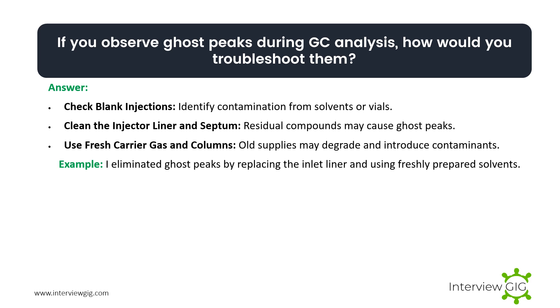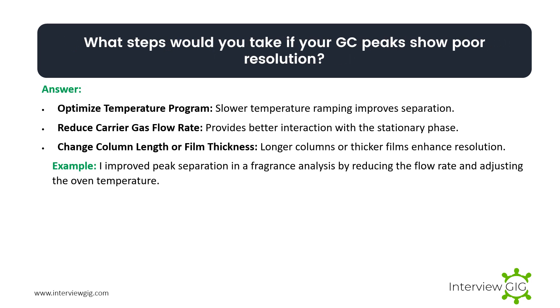If you observe ghost peaks during GC analysis, how would you troubleshoot them? Check blank injections to identify contamination from solvents or vials. Clean the injector liner and septum, as residual compounds may cause ghost peaks. Use fresh carrier gas and columns, as old supplies may degrade and introduce contaminants. Example: I eliminated ghost peaks by replacing the inlet liner and using freshly prepared solvents.